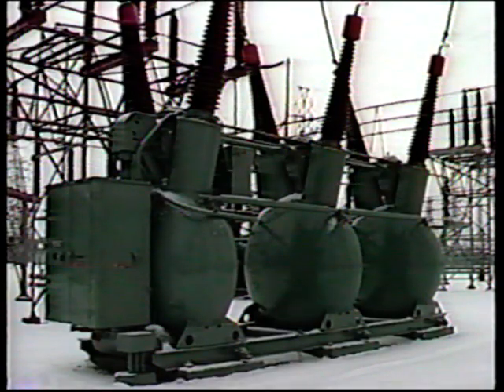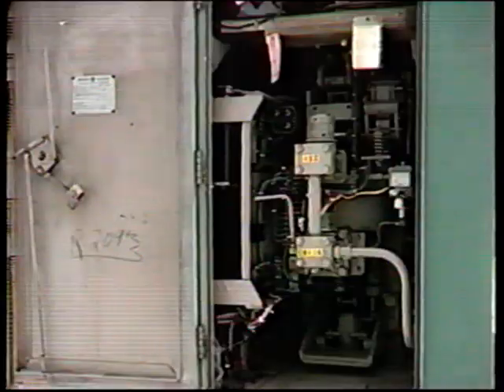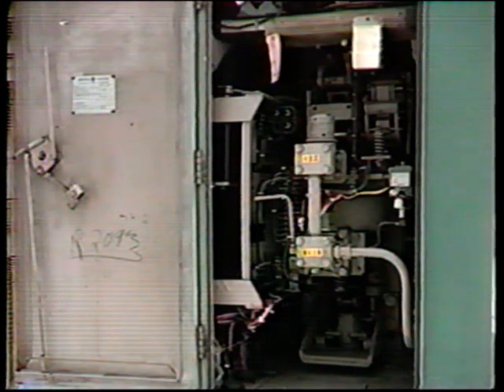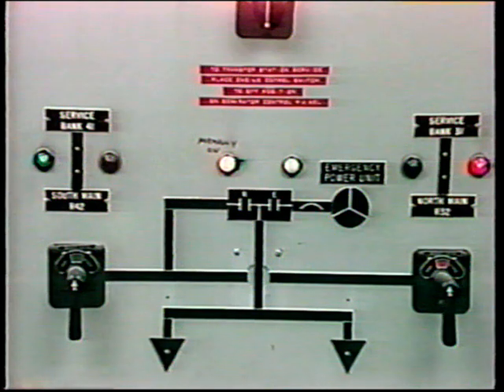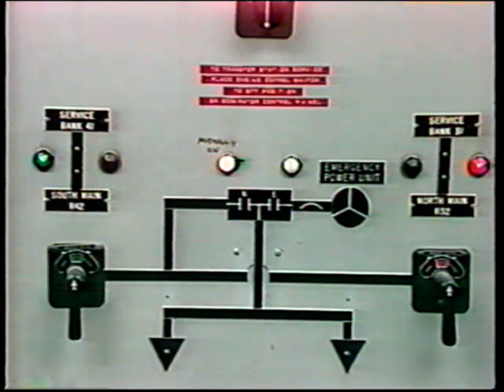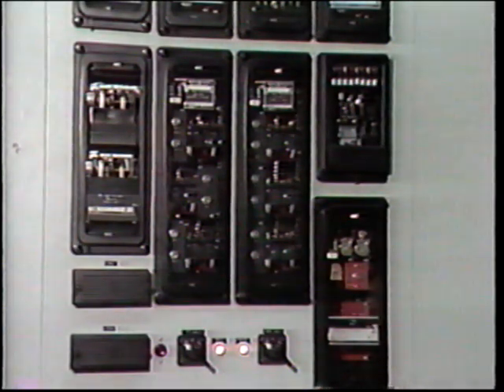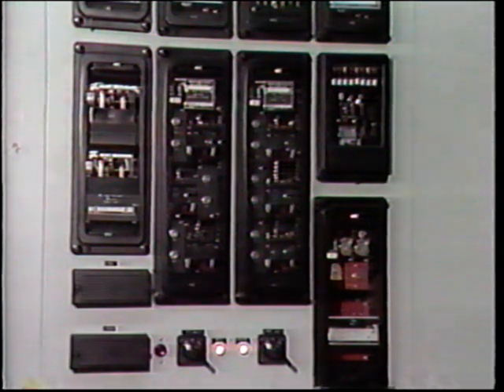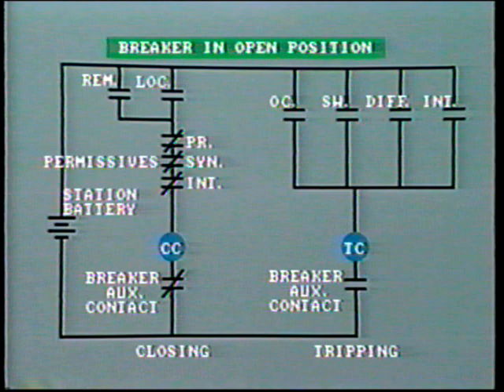As we've already mentioned, circuit breaker components may be physically far apart. The closing and tripping coils are located adjacent to the breaker. The manual switching contacts may be located at some considerable distance on the control panel. The protection relay contacts inside the relay may be in yet another location. However, from an electrical point of view, the breaker control circuit looks like this. The DC positive and negative may be drawn horizontally or vertically. It really makes no difference. You soon get used to working through the circuit to determine the sequence of events.